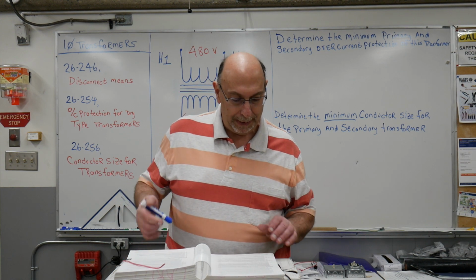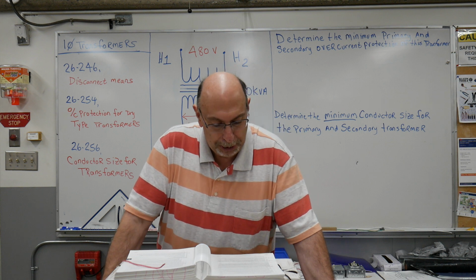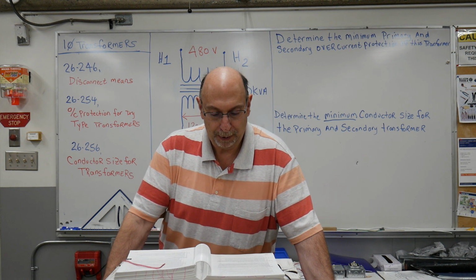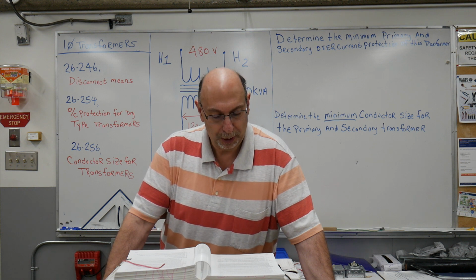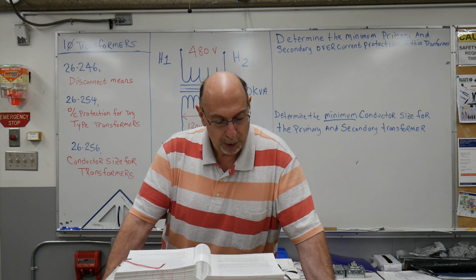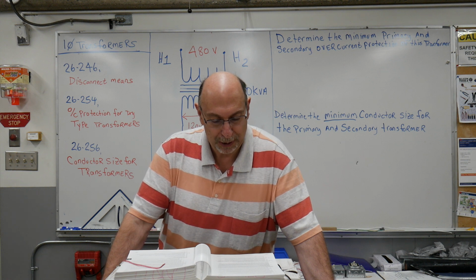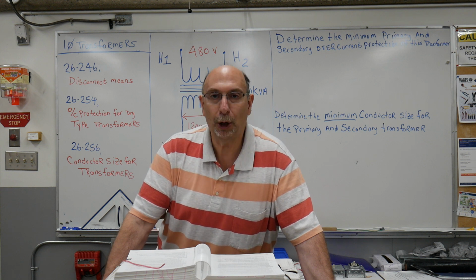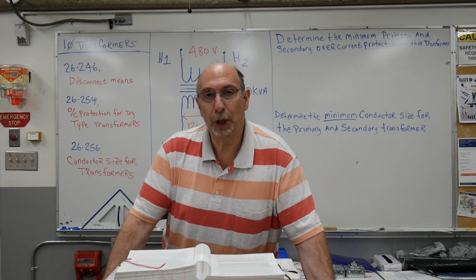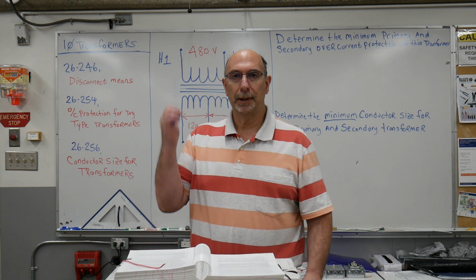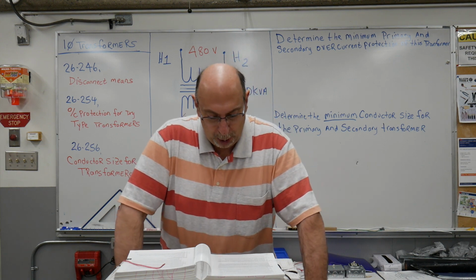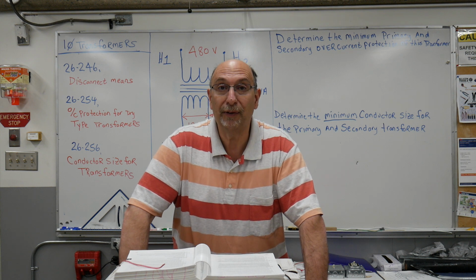So 254 sub-rule 1 states, except as permitted by sub-rule 2, each ungrounded conductor of the transformer feeder or branch circuit supplying the transformer shall be provided with overcurrent protection rated or set at not more than 125% of the rated primary current of the transformer. And this primary overcurrent device shall be considered as protecting secondary conductors rated at 125% or more of the rated secondary current. So our primary fuse or overcurrent device can protect the secondary conductors of the transformer as long as the conductors are rated at 125% or more.